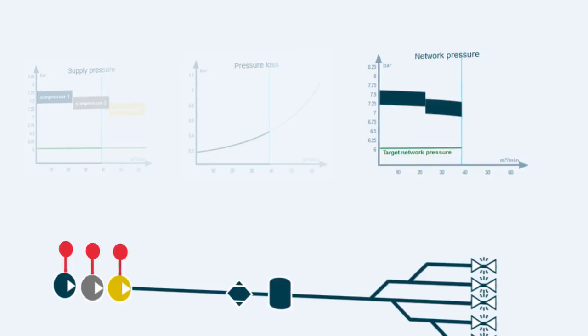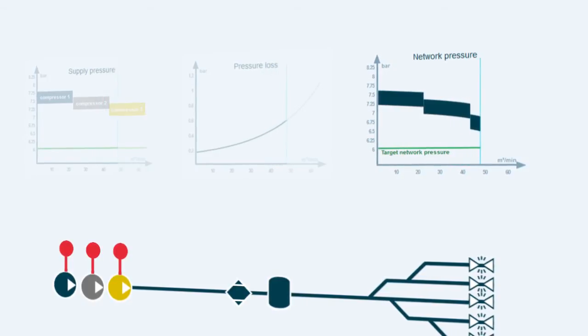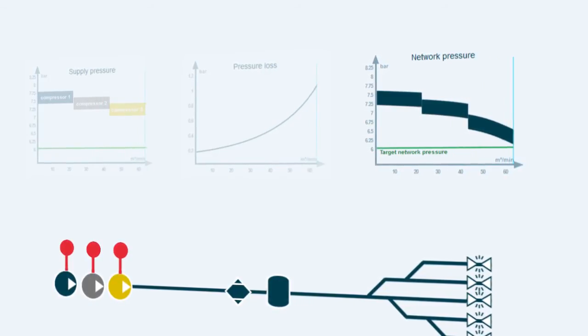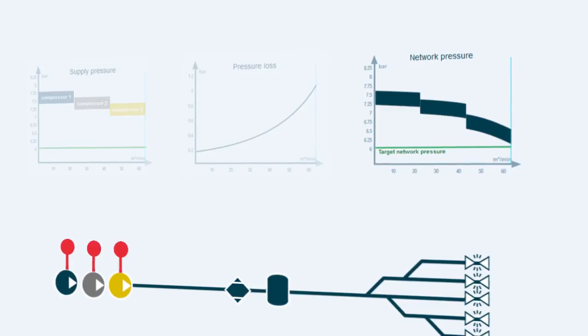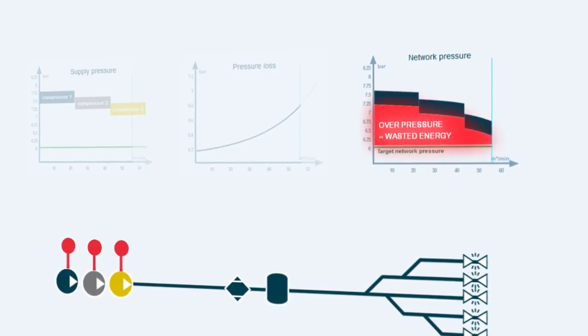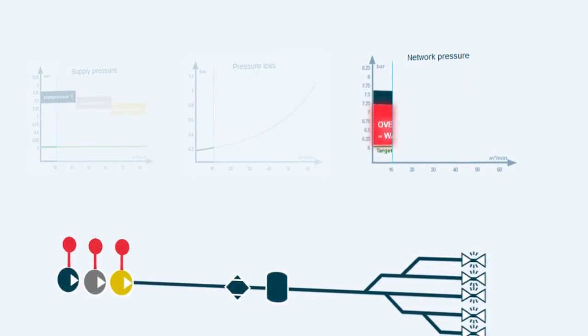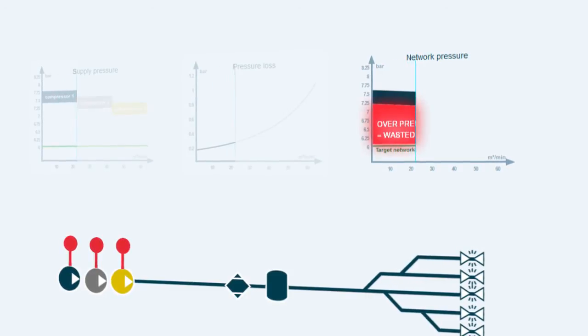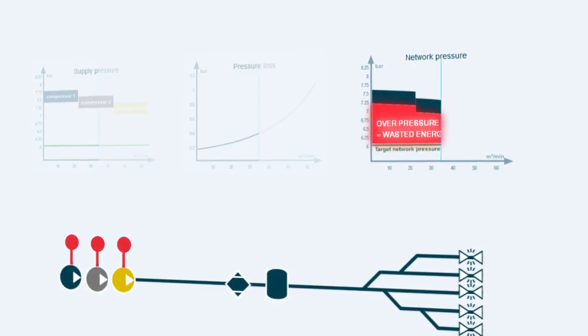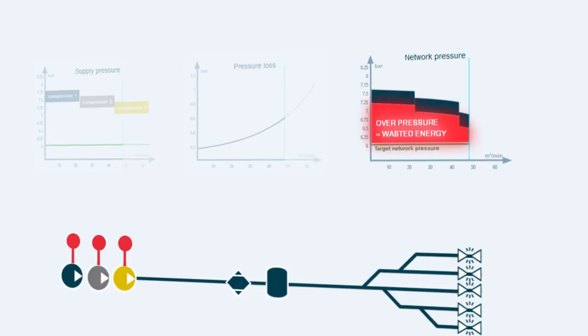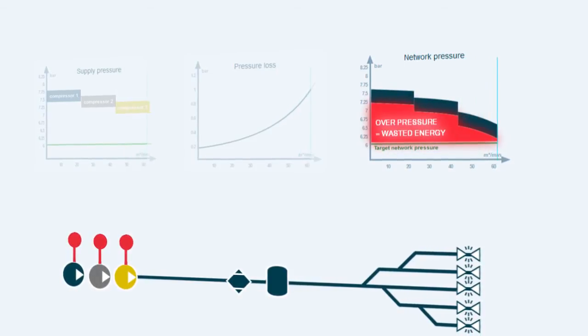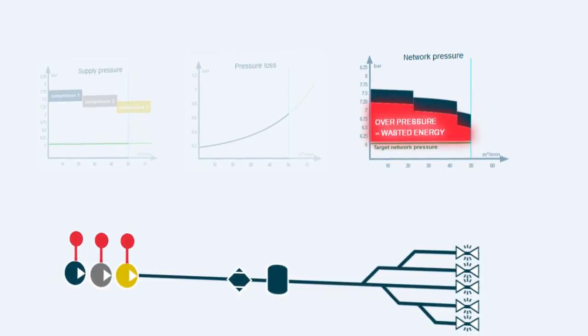The pressure settings of the compressors should be high enough to secure the minimum pressure level at maximum consumption. The outcome is that an unnecessarily high pressure level practically always exists in the system. Production plants are accustomed to maintaining a high pressure level to avoid problems in production. An unnecessarily high pressure level is a waste of energy.